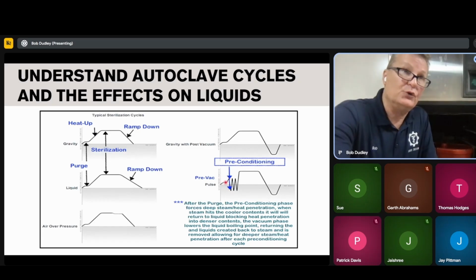So if you have more than 7%, that's that much more humidity, and it's going to create that much more rain within it that it has to expel and try to overcome. That's why if your autoclave isn't working right, especially on the gravity, if you're using this for your waste cycle, it takes a lot longer to overcome that. Where here, this is very violent. So as you push it in, it's going to create a barrier.